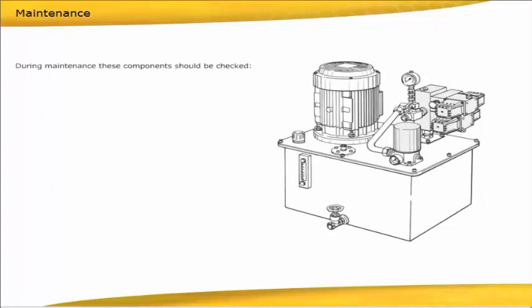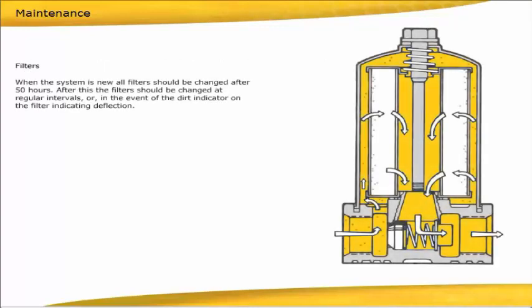During maintenance, these components should be checked. Click on the hotspots to learn more. Filters: When the system is new, all filters should be changed after 50 hours. After this, the filters should be changed at regular intervals, or in the event of the dirt indicator on the filter indicating deflection.